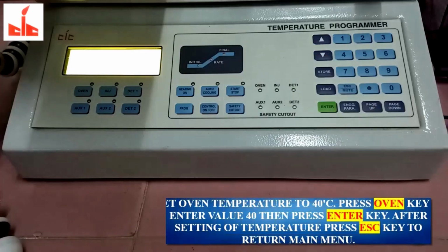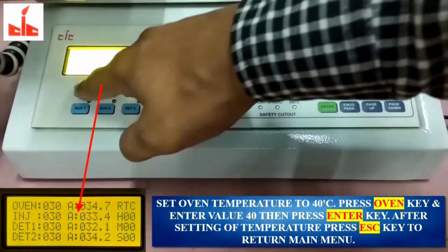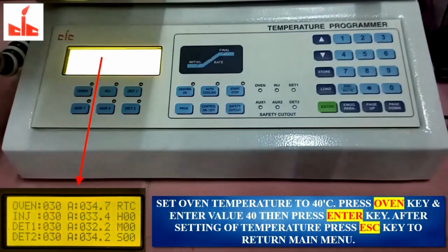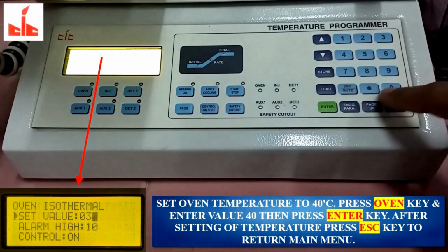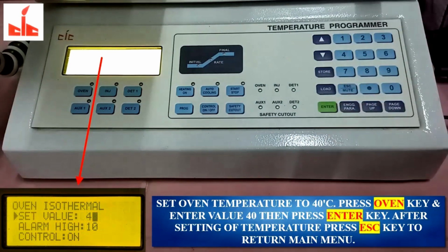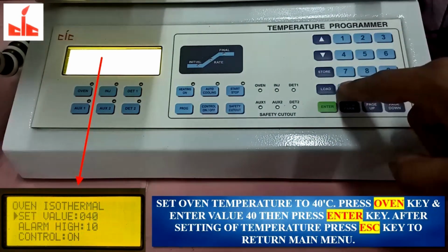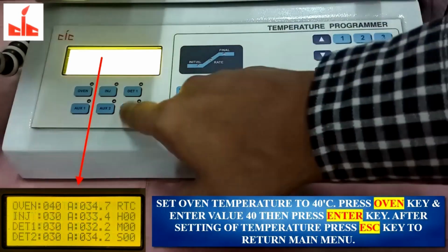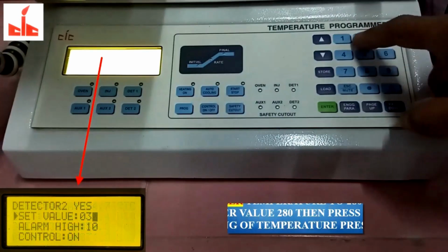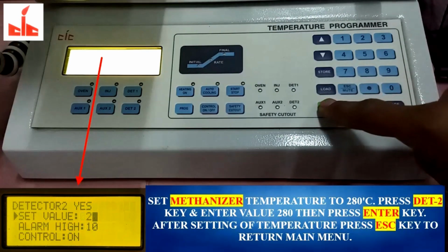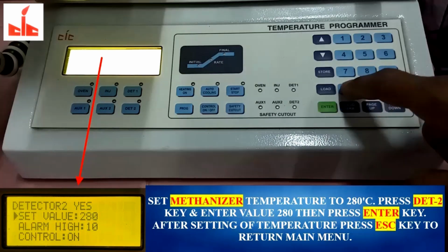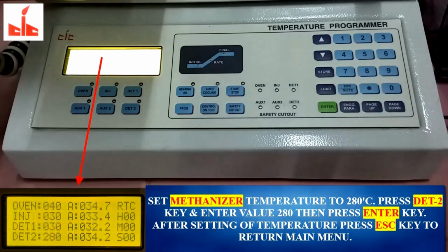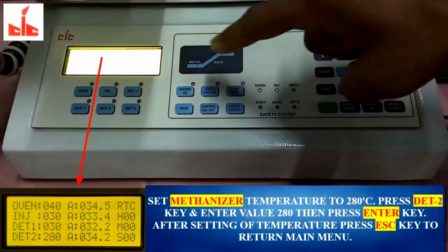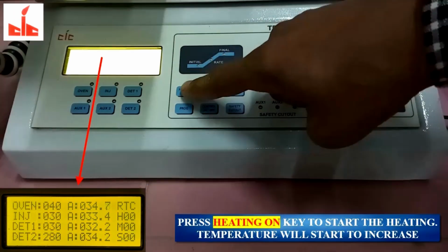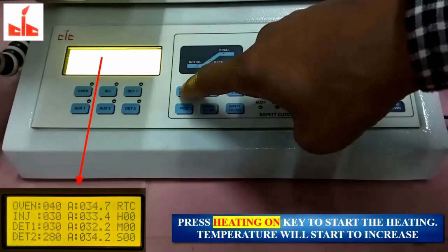Set the oven temperature to 40 degrees centigrade. To set, press oven key, and enter value 40, then press enter key. After setting of temperature, press escape key, to return main menu. Set methanizer temperature to 280 degrees centigrade. Press detector 2 key and enter value 280, then press enter key. After setting of temperature, press escape key to return main menu.